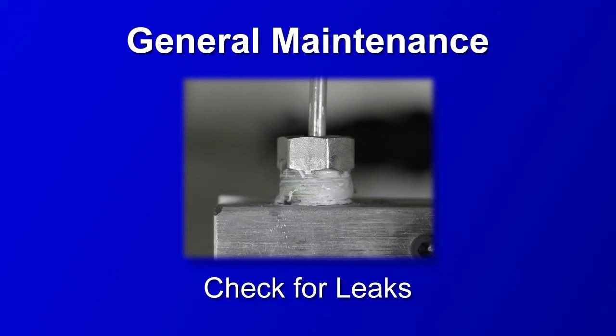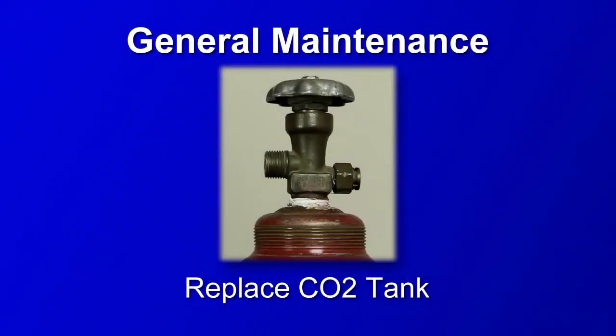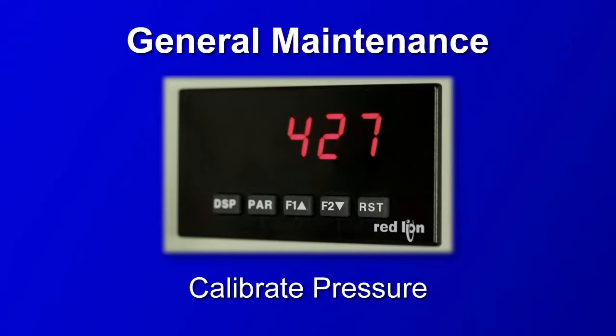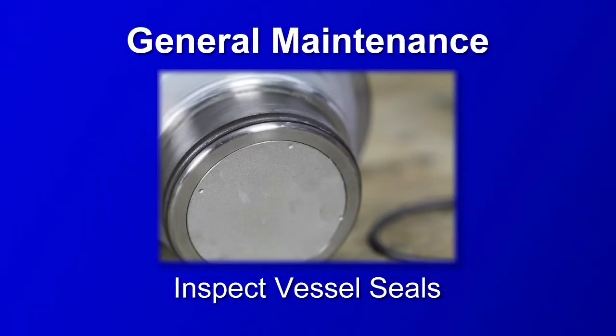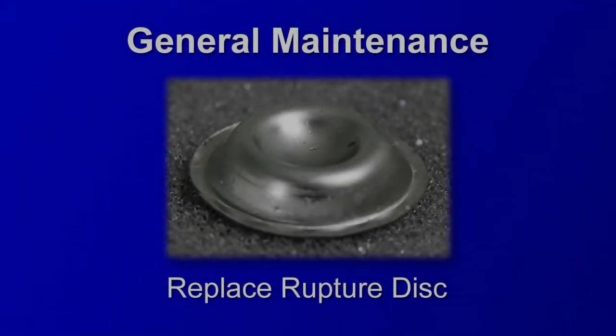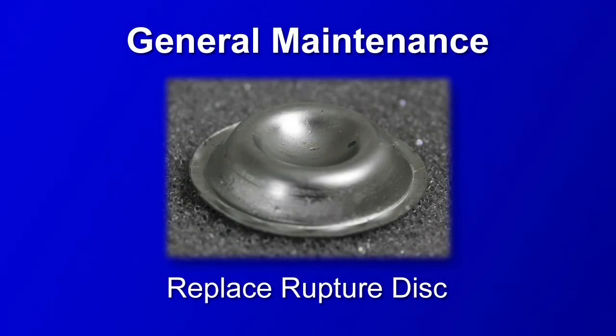and other connections. We suggest using Snoop or equivalent. Replace the CO2 tank when you can no longer achieve pressure. The pressure calibration should be checked yearly. A Heise gauge is recommended for this purpose. Sample vessel seals should be inspected regularly for nicks and cuts. If any damage is found, the seal should be replaced. The rupture disc will weaken over time from operation of the unit caused by flexing of the pressure load on the disc. This item should be replaced on a yearly basis.